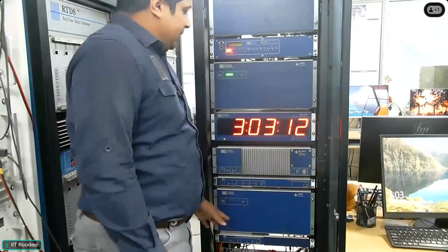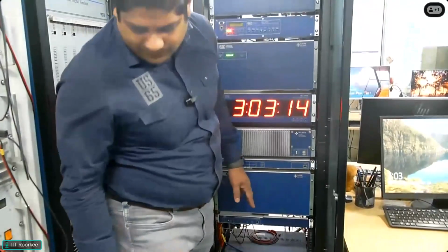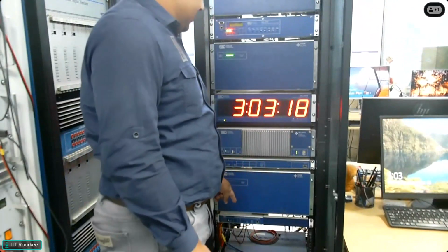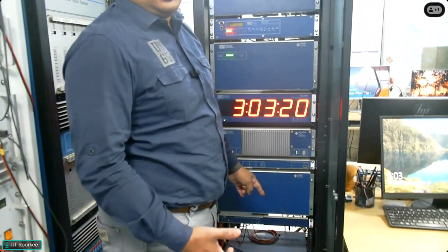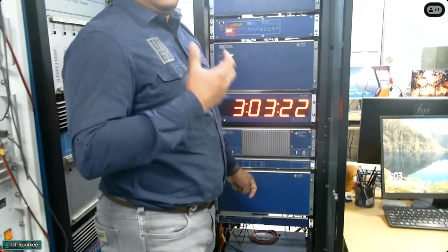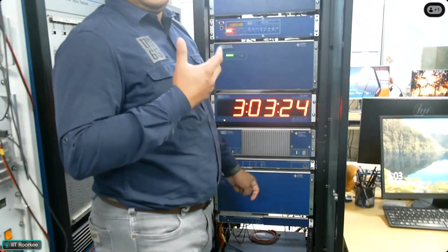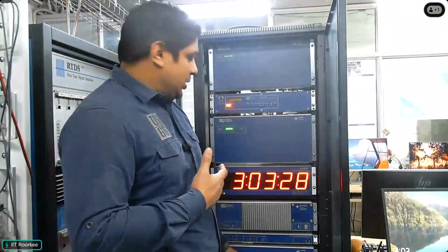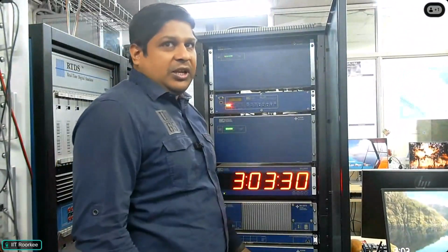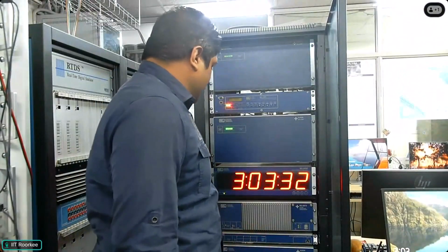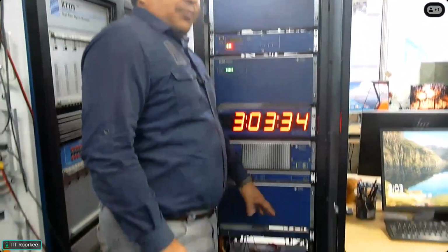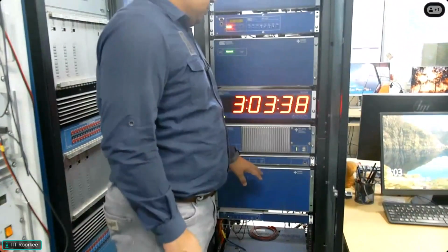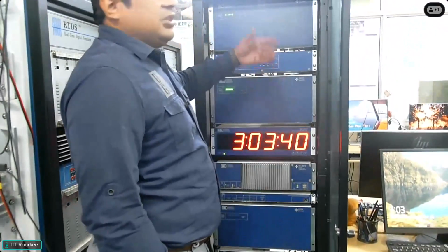Three voltages and 3 currents we give to this amplifier. We can give 6 currents also based on our function. If we are only working on the fault and protection functionality, we generally give 6 currents. And here we are giving 3 voltages and 3 currents. After amplification, we give them to these PMU devices. I will show the connections in the backside.